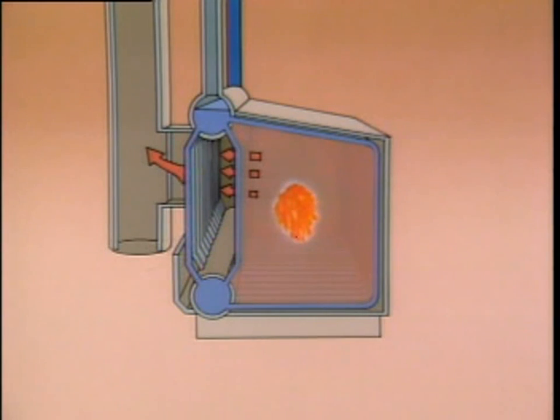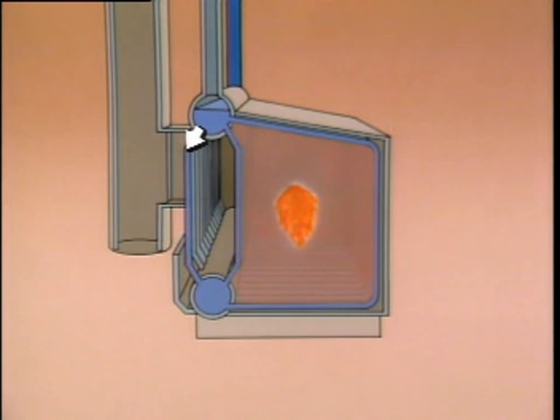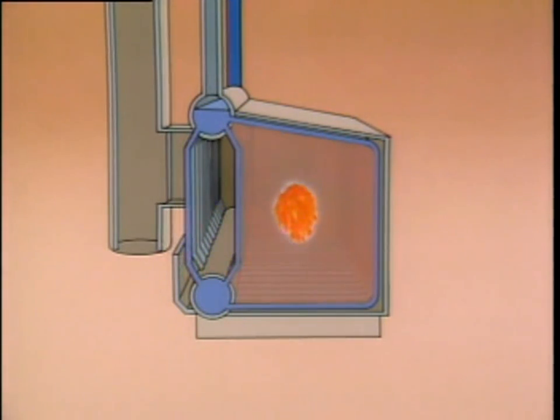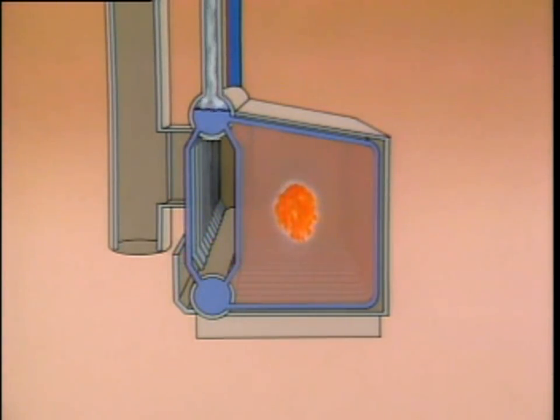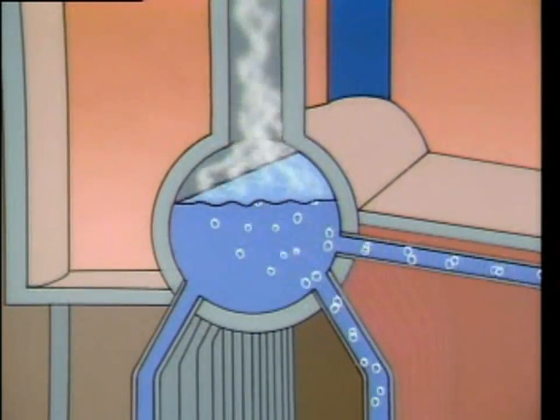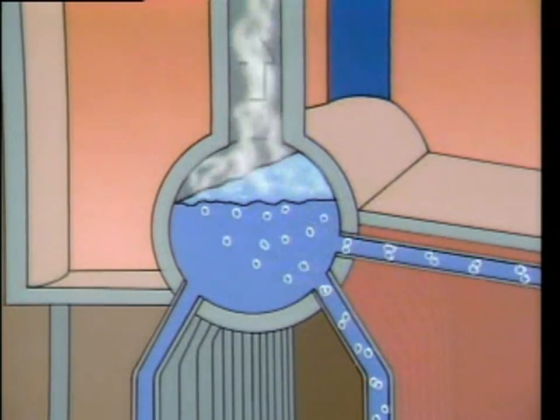The combustion gases then flow out of the boiler. Water circulates from the upper drum through the water tubes and into the lower drum, which is often referred to as the mud drum. From the lower drum, water is distributed to the water tubes surrounding the combustion area. As the water in the tubes is heated, a steam-water mixture is produced. The steam-water mixture enters the upper drum, where the steam is separated from the water and routed through the steam outlet and into the plant.